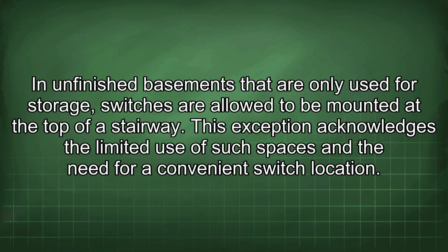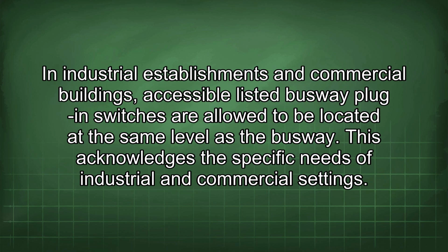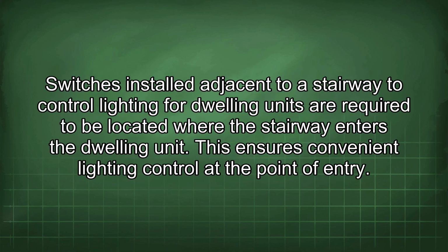In unfinished basements that are only used for storage, switches are allowed to be mounted at the top of a stairway. This exception acknowledges the limited use of such spaces and the need for a convenient switch location. In industrial establishments and commercial buildings, accessible listed busway plug-in switches are allowed to be located at the same level as the busway. This acknowledges the specific needs of industrial and commercial settings. Switches installed adjacent to a stairway to control lighting for dwelling units are required to be located where the stairway enters the dwelling unit. This ensures convenient lighting control at the point of entry.